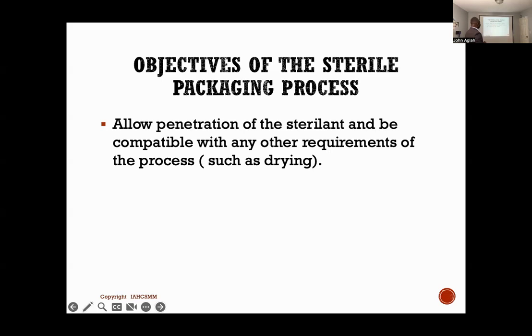All right, so allow penetration of the sterilants and be compatible with. This means that the packages go through various sterilants. Instrumentations are exposed to either steam sterilization. Steam will be the sterilant in terms of steam sterilization. When we talk about low temperature sterilization, the sterilant will be hydrogen peroxide. Of course, there are different types of low temperature sterilants we will talk about. One is ethylene oxide and ozone. That chemical that comes through the package to get onto the instrumentation is what we call sterilants. That sterilant is what kills the HIVs, the hepatitis B that is exposed on this medical device. Okay, not the machine itself. It's the sterilant that does that through the machines. So when we get to sterilization, we'll talk about that.